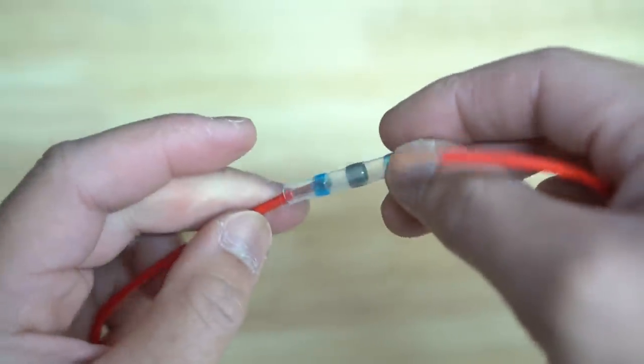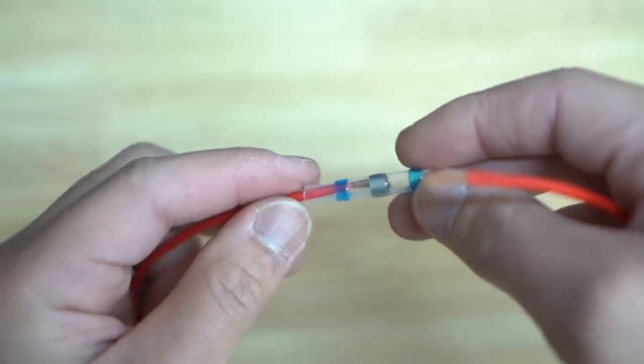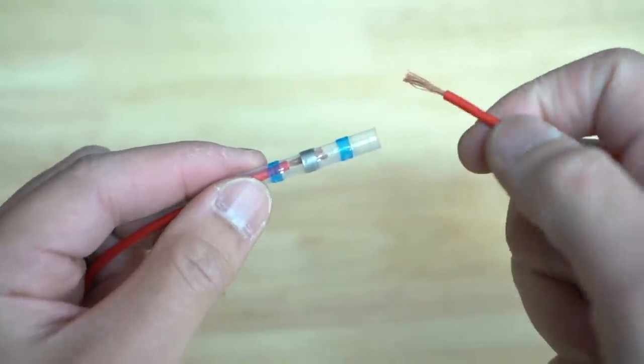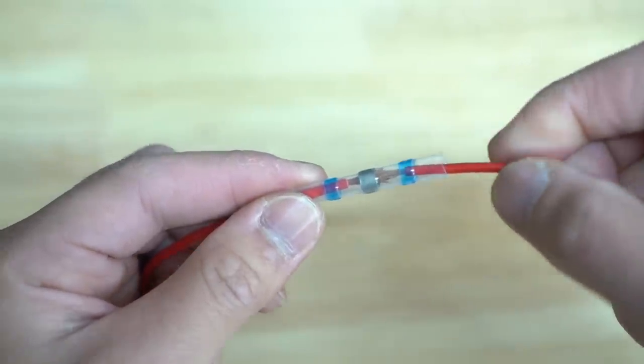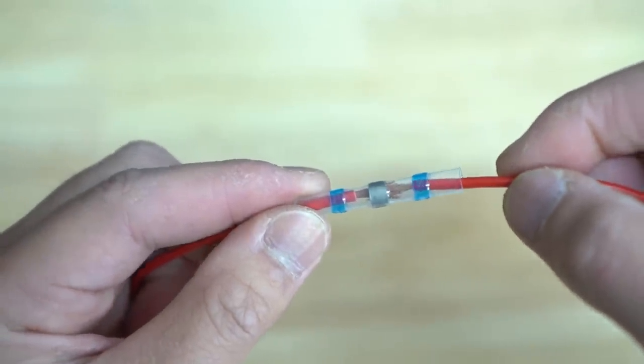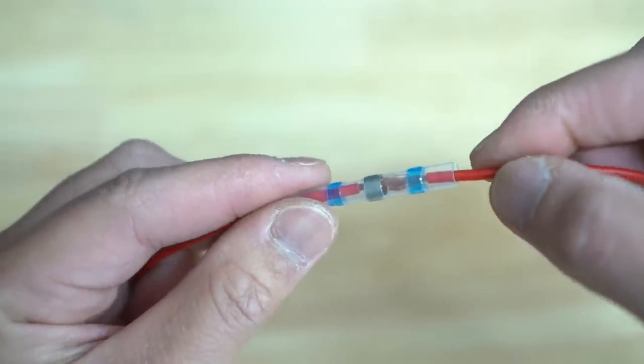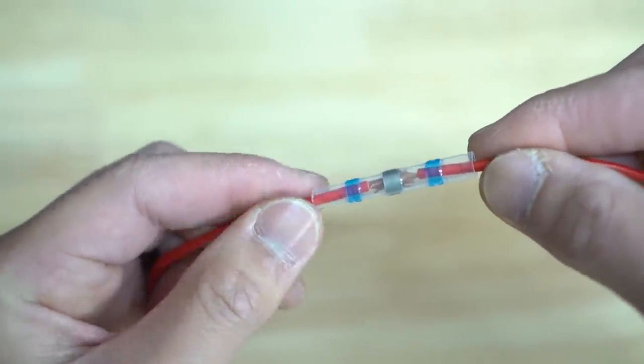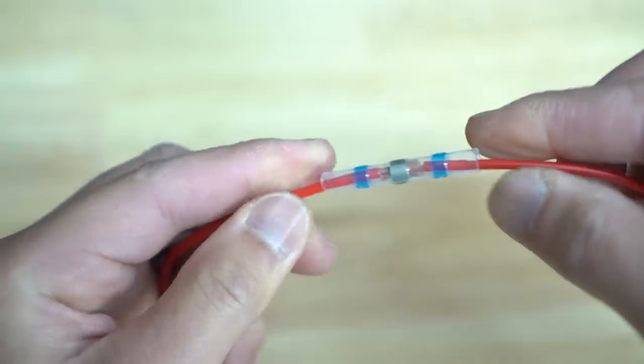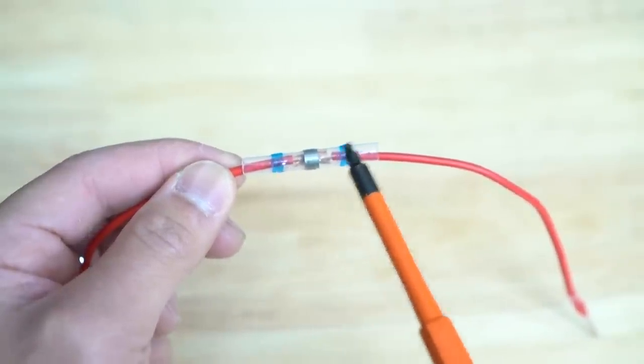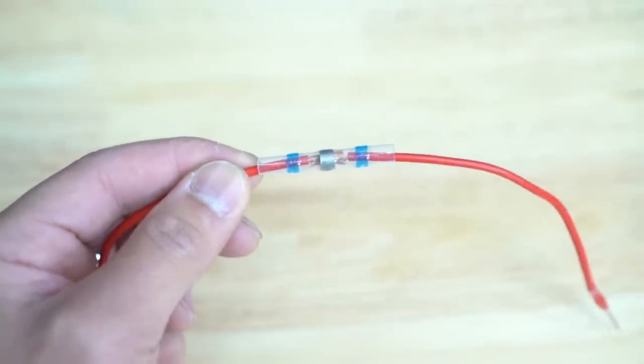Slide this through. Just make sure that all the strands go inside the tube. Like that. You're going to do the same thing on the other side. So notice how all the wires just connect right there. And you want to meet those connections right in the middle. Just like that. So now that the insulation passes the blue ring on both sides, now we can use the heat gun and melt that solder to fully have a connection.